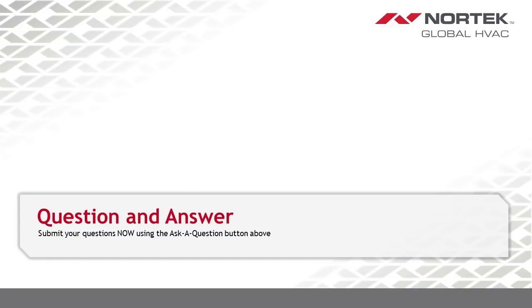Question here for manufactured housing specifically. We mentioned the testing was done at 0.5 static for residential product. For manufactured housing, it's really run at 0.3. So equipment we're building—the 80% single stage, the 95% two stage—we're rating them both at residential statics and at manufactured housing statics, so they'll be able to be sold in both applications. But it's important to note that the manufactured housing requirement is 0.3, whereas the residential requirement is 0.5.